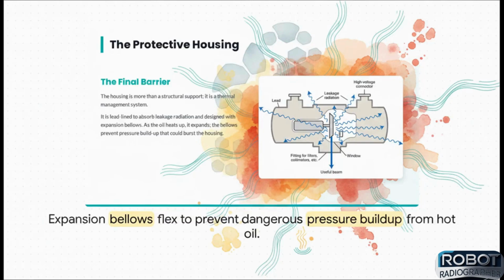All that hot oil is held inside the protective housing. And this thing is way more than just a simple case. Of course, it's lead-lined to stop any stray radiation, but it also has a really cool feature: an expansion bellows. You see, as the oil heats up, it expands, and this bellows acts like a lung, flexing to prevent a dangerous pressure buildup that could literally rupture the entire unit.